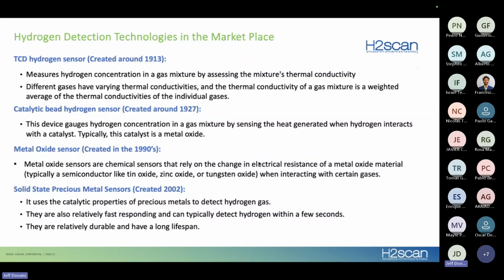So these are common hydrogen detectors that are in the marketplace. This is what we see in battery rooms mostly. We see TCDs, or thermal conductivity detectors, catalytic bead sensors, metal oxide sensors, and solid state precious metal sensors. And you can see the date that they were all created. So the oldest, of course, is the TCD, created around 1913. And this basically measures the gas mixture by assessing the thermal conductivity. And then of course, varying gases have different conductivities, and it's weighted against the average. So this is a very fast sensor. It's been around a long time, but it also has a lot of cross sensitivities as well.